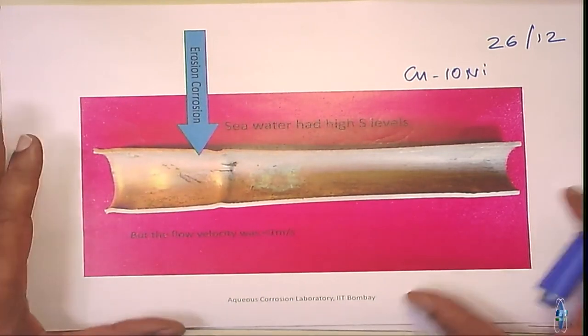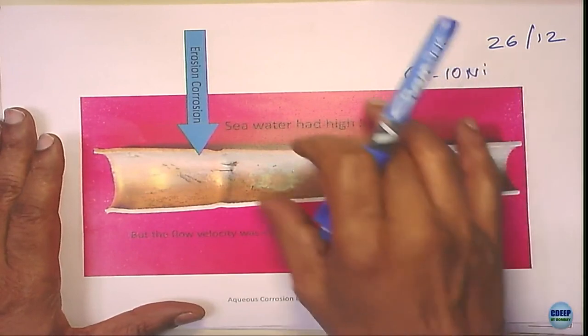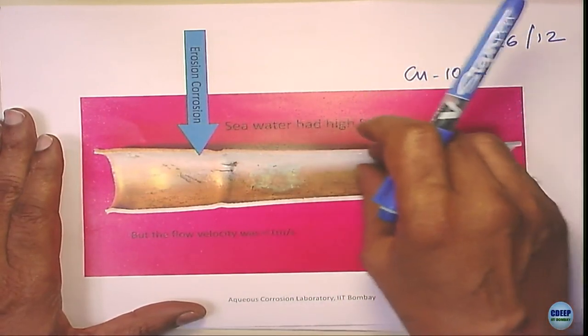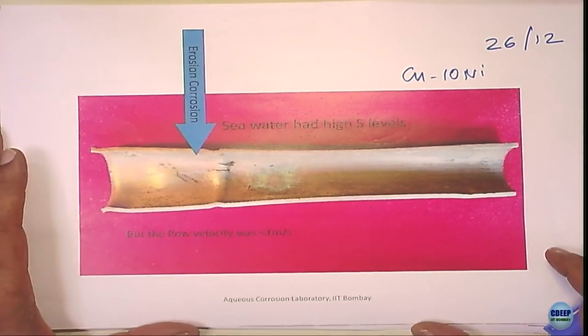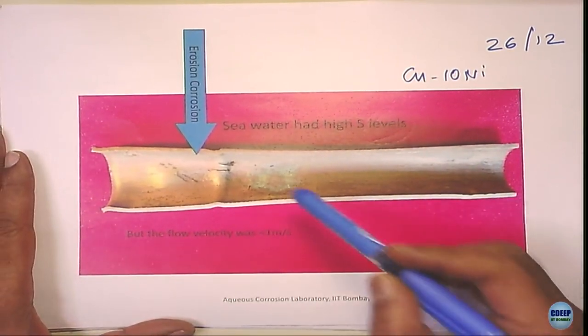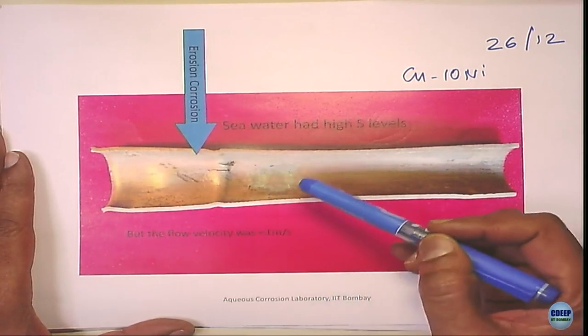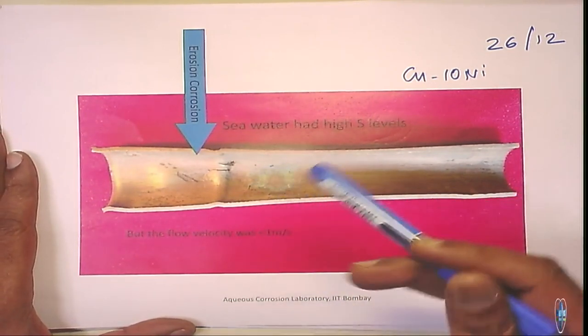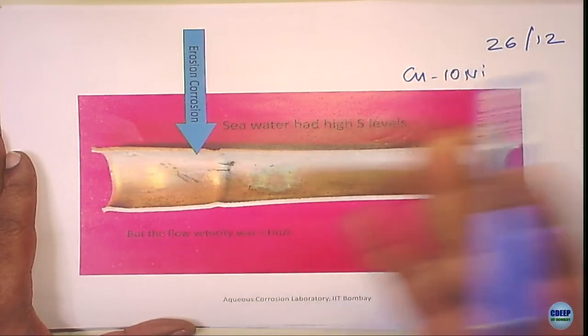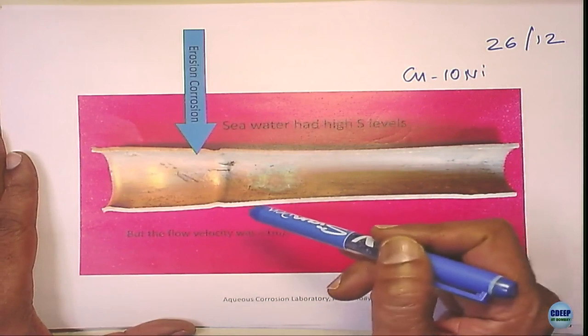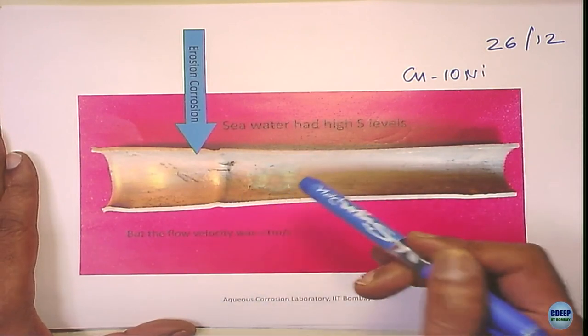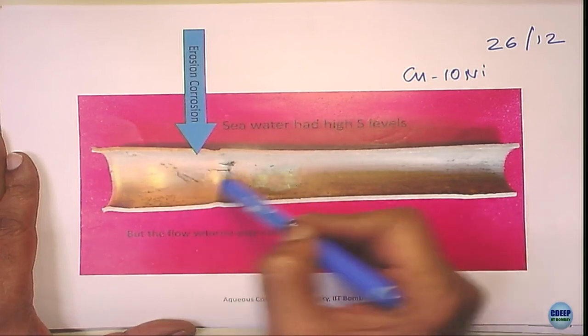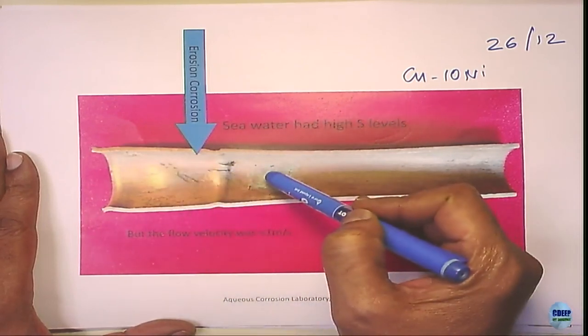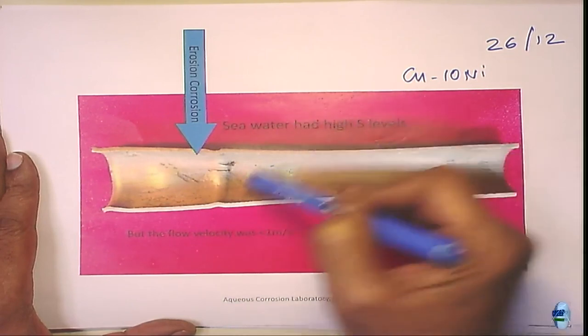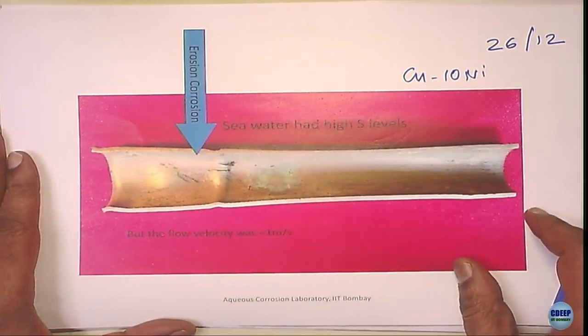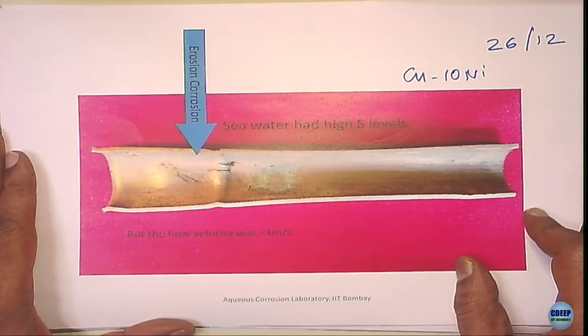So a whole lot of people were arguing that it is de-alloying primarily, because you see a nice green color and some kind of deposits taking place. But if you look very closely, you see these are not. There is de-alloying, but that is not the determining factor. There are two damage mechanisms operating, no doubt about it. De-alloying is operating, but what is the primary or faster damaging mechanism? The faster damaging mechanism, in my view, has been more of erosion-corrosion damage assisted by these sand particles.